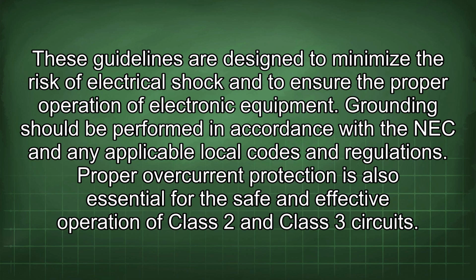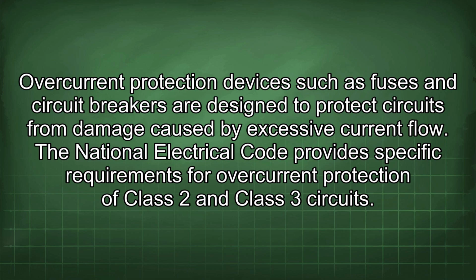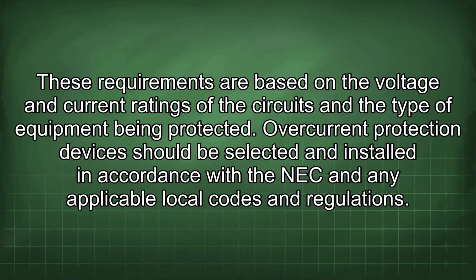Proper overcurrent protection is also essential for the safe and effective operation of Class 2 and Class 3 circuits. Overcurrent protection devices such as fuses and circuit breakers are designed to protect circuits from damage caused by excessive current flow. The National Electrical Code provides specific requirements for overcurrent protection of Class 2 and Class 3 circuits. These requirements are based on the voltage and current ratings of the circuits and the type of equipment being protected. Overcurrent protection devices should be selected and installed in accordance with the NEC and any applicable local codes and regulations.